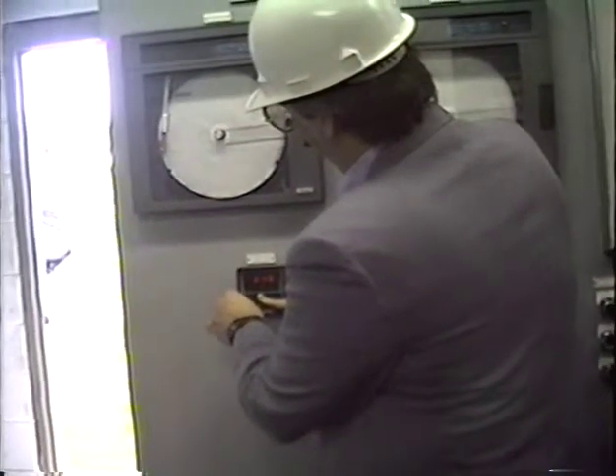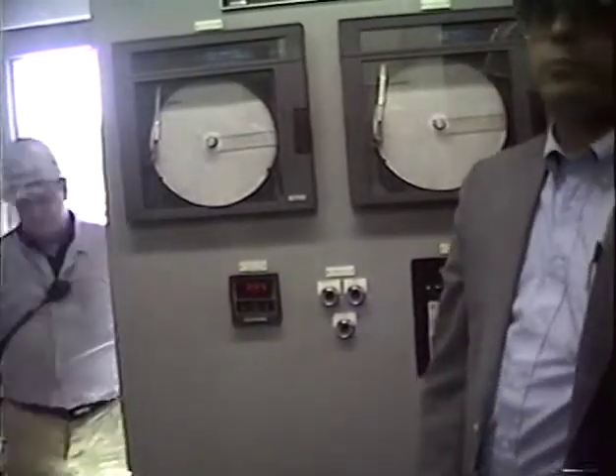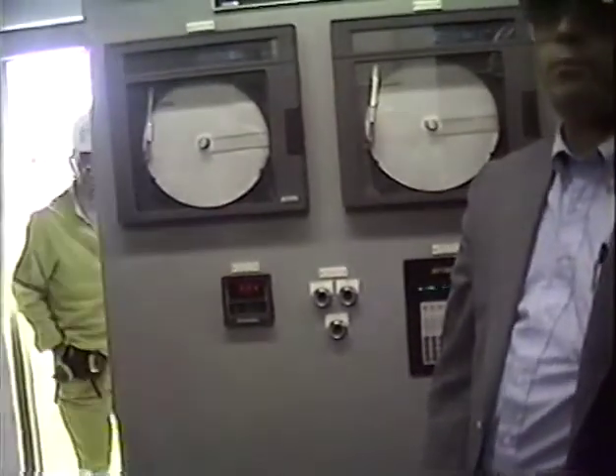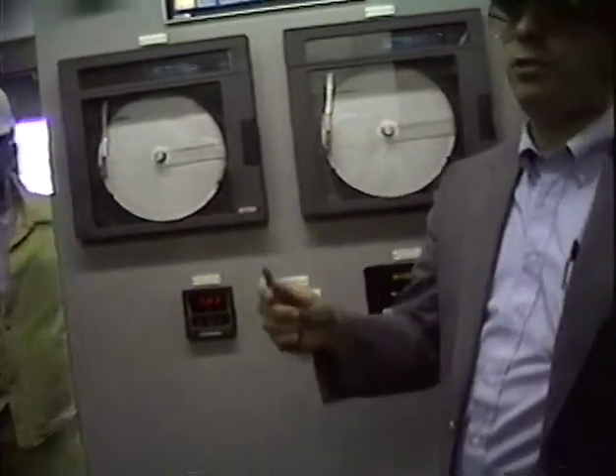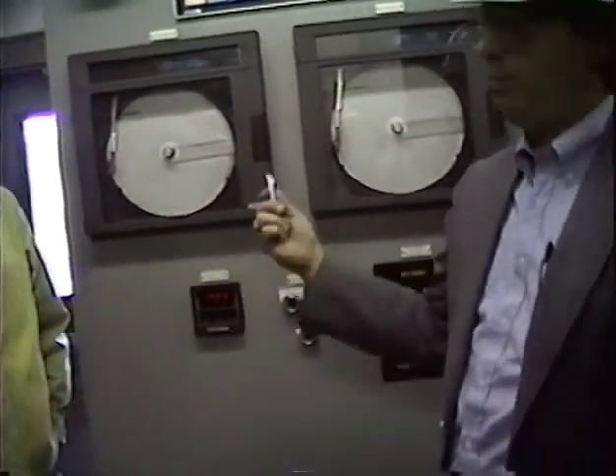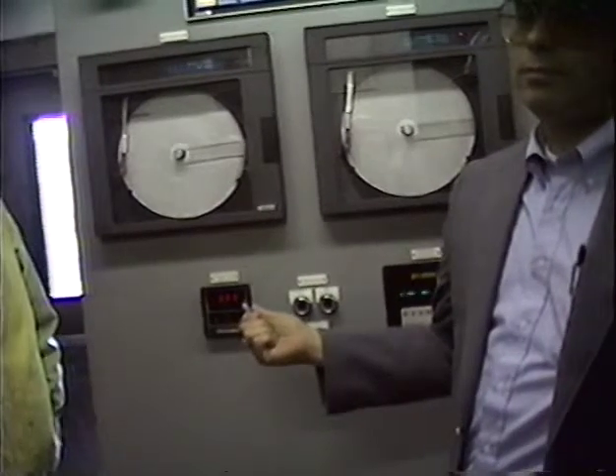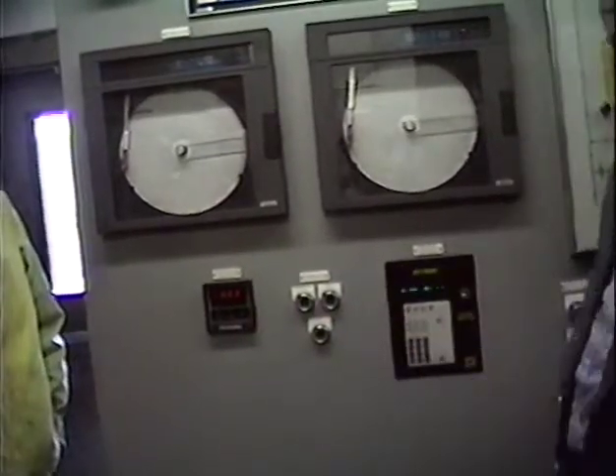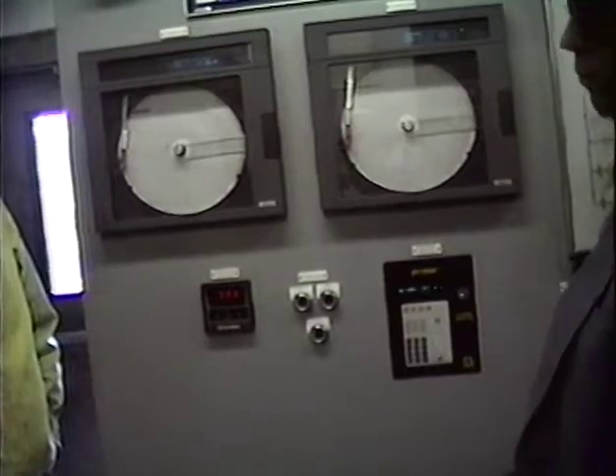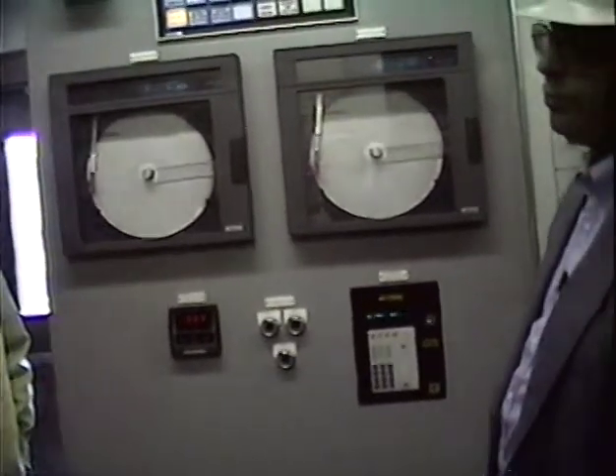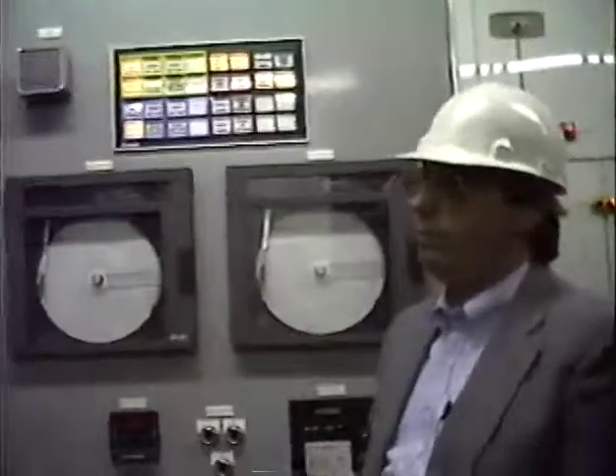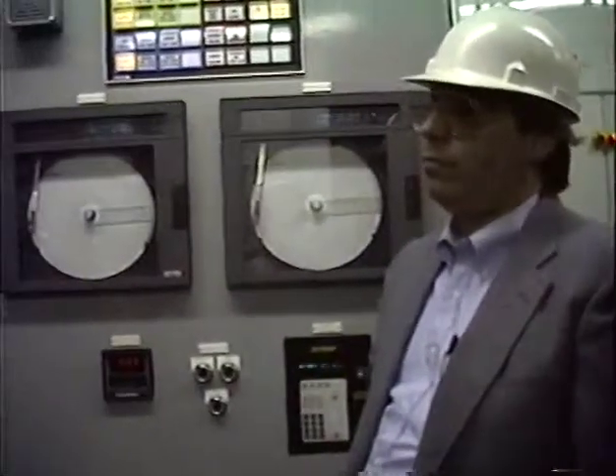I hope when you get the fire alarm that the tempering air damper doesn't try to open, and then you'll feed the fire if there is one. Yeah. If the fire creates a temperature of 250, the damper's going to go open. You don't want that going into the baghouse, that's for sure. Why would you want to pack the bags? Besides that, that'll put fresh air into your baghouse and it'll cut your draft out that's going in. Yeah, whether it comes in through the tempering air damper or comes in through the shed, air is air, right? It's going to get you no matter what.